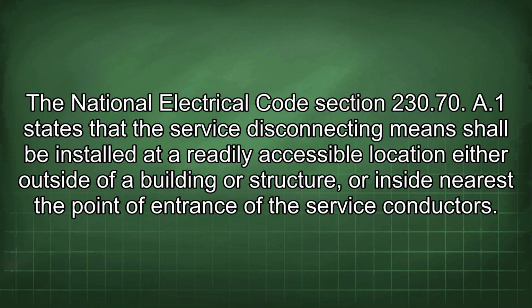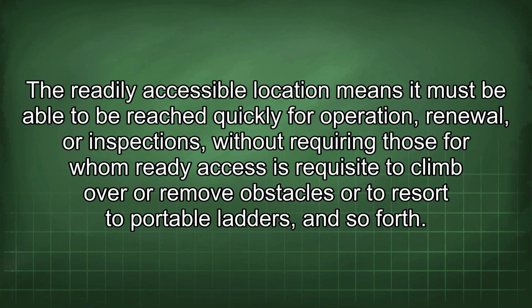The National Electrical Code Section 230.70 A1 states that the service disconnecting means shall be installed at a readily accessible location either outside of a building or structure or inside nearest the point of entrance of the service conductors. The readily accessible location means it must be able to be reached quickly for operation, renewal, or inspections without requiring those for whom ready access is requisite to climb over or remove obstacles or to resort to portable ladders, and so forth.